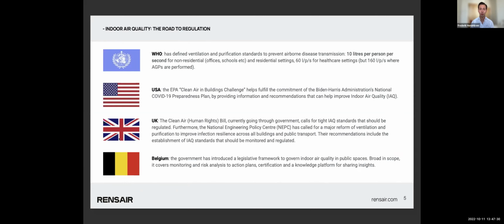I think it's also worth noting that these numbers are on a per person basis, where many historically think of air changes per hour in a room as a function of the size of the room. Really, what you should be thinking about is how many people are in a space at any given time, and ensure there's sufficient ventilation for that amount of people. And you can see here that the recommendation for aerosol generating procedures is all the way up at 160.